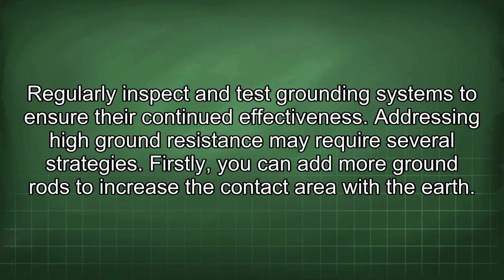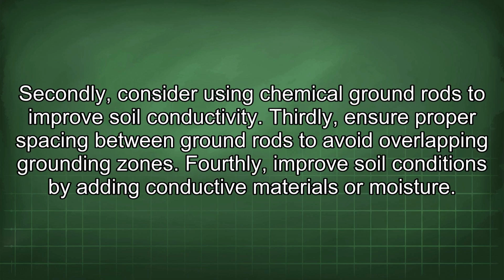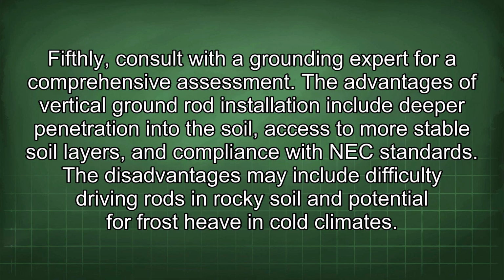Addressing high ground resistance may require several strategies. Firstly, you can add more ground rods to increase the contact area with the earth. Secondly, consider using chemical ground rods to improve soil conductivity. Thirdly, ensure proper spacing between ground rods to avoid overlapping grounding zones. Fourthly, improve soil conditions by adding conductive materials or moisture. Fifthly, consult with a grounding expert for a comprehensive assessment.